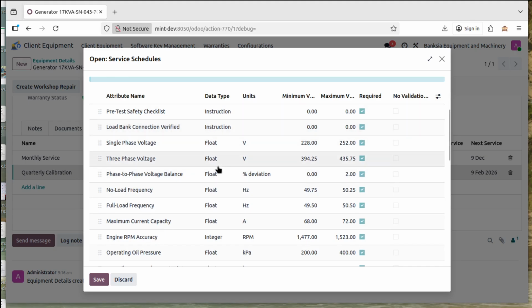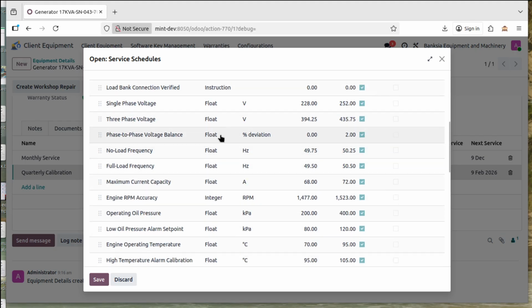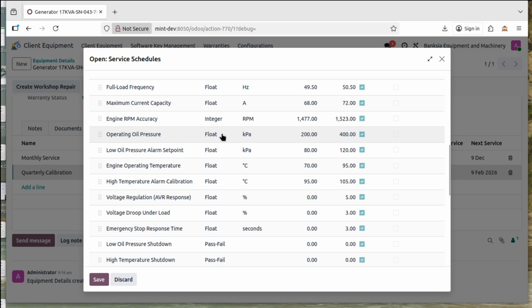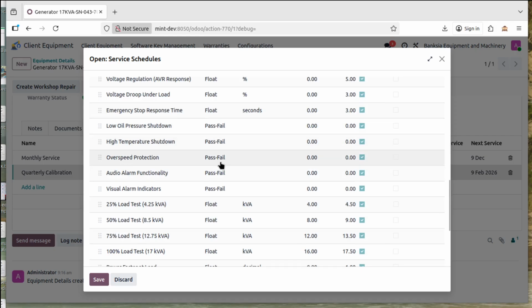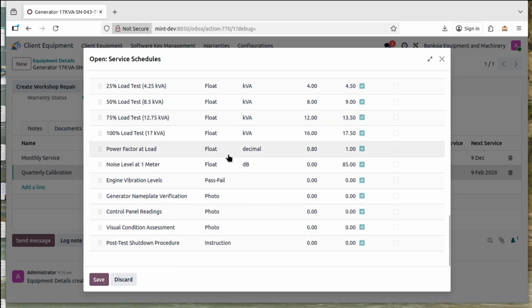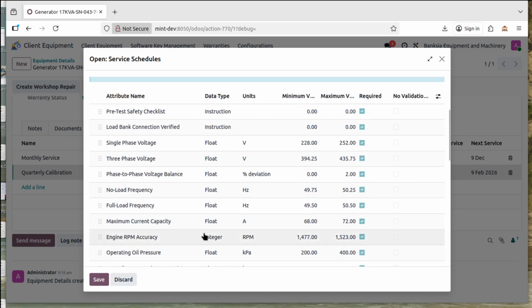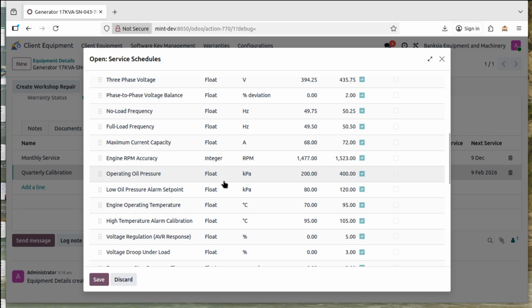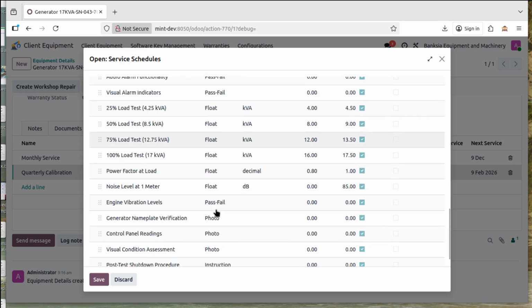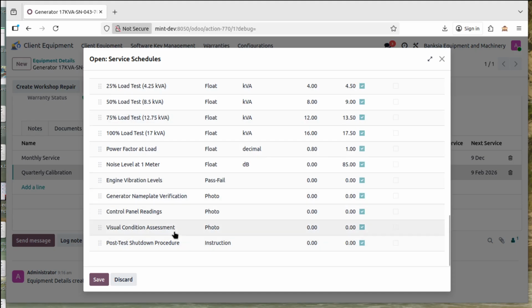You'll notice some of these are instructions, some are floats - meaning they can handle a decimal point. Some are integers, which are just whole numbers and don't handle decimal points as well. Some are pass-fail, just to tick off that you've done them. We've also got photos in here - so if you require an image to be taken while you're out on site doing the calibration test, or any other check, you can add those photos in there too. So our main data types are instructions, floats, integers, pass-fail, and photos.